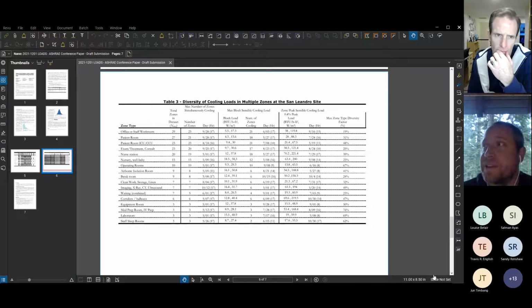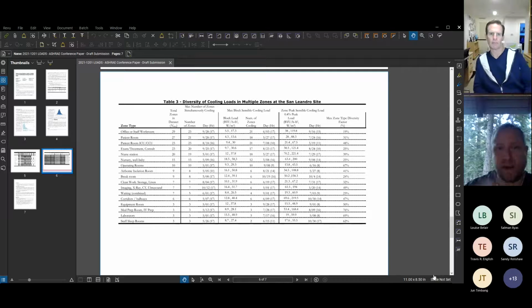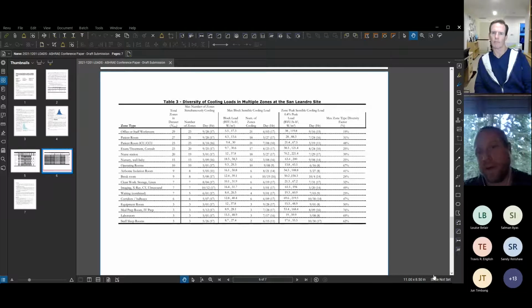We'll definitely look into that, especially for some of these spaces that may not be reheating and subcooling. I'd say one of the biggest things coming out of the data in general is noticing controls issues, which we briefly mentioned on our kickoff call. One of the things we've done up to this point to help clean that up is, at this specific site, in the winter months we're noticing some really highly oscillating room conditions.